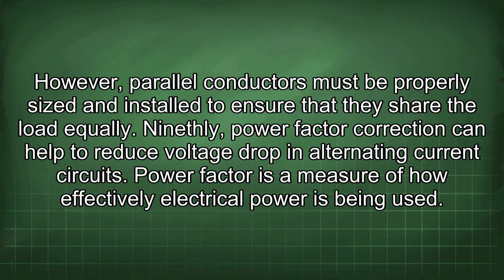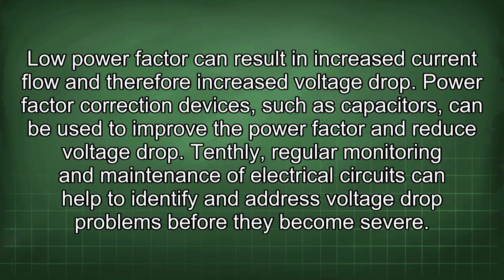Ninthly, power factor correction can help to reduce voltage drop in alternating current circuits. Power factor is a measure of how effectively electrical power is being used. Low power factor can result in increased current flow and therefore increased voltage drop. Power factor correction devices, such as capacitors, can be used to improve the power factor and reduce voltage drop.